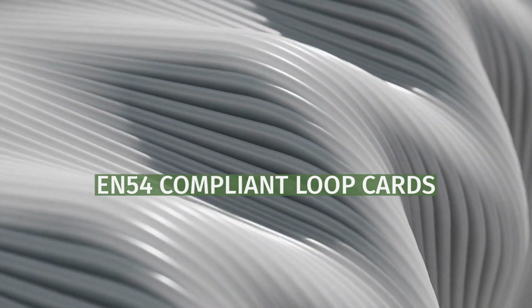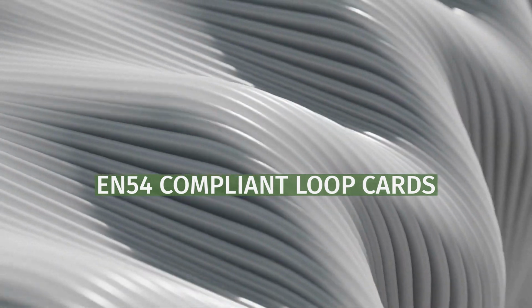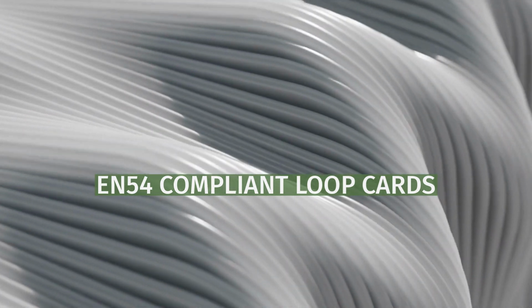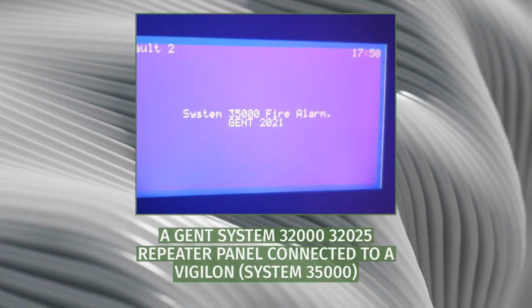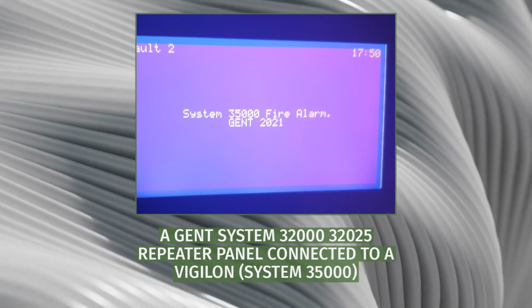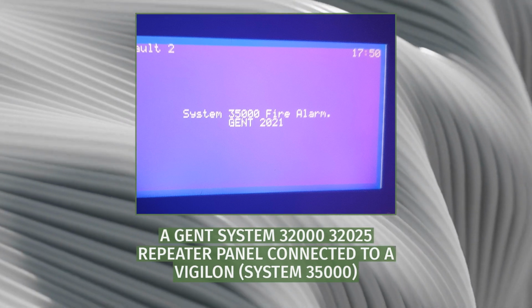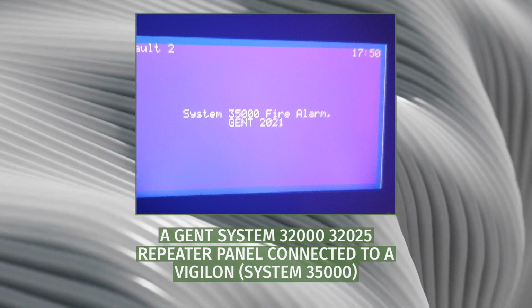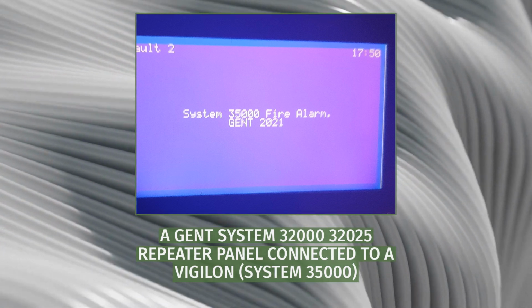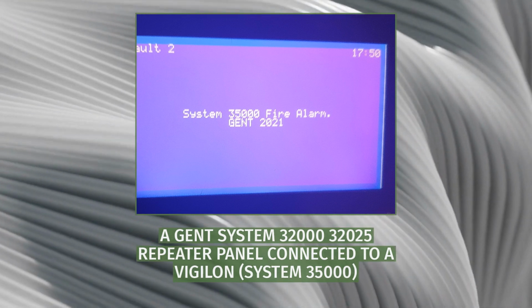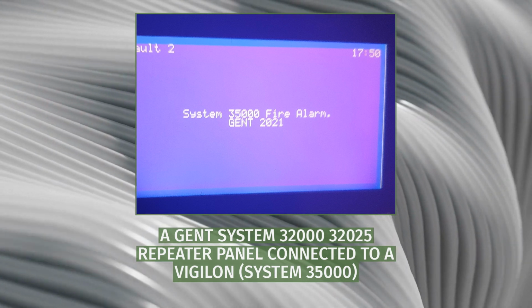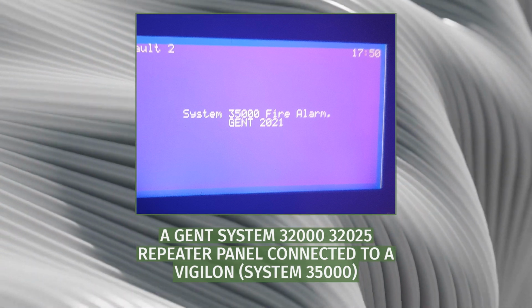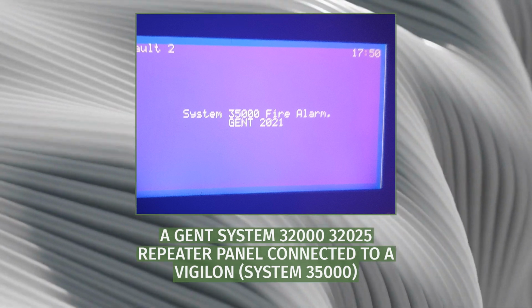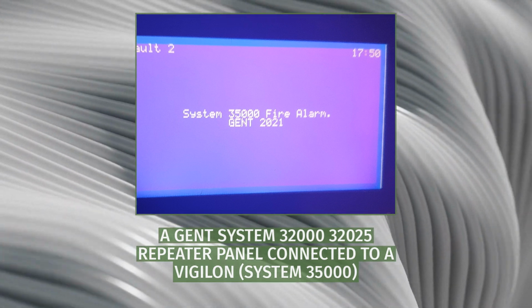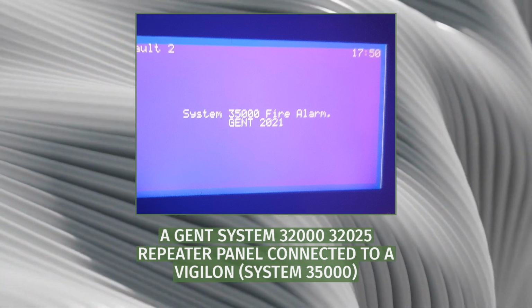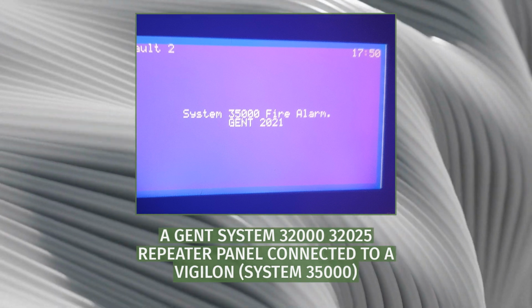In 2014, after the release of the high-power VID S-Cubed and S-Quad devices, Gent released a more powerful loop card that was capable of taking advantage of the full power of these devices. However, despite using the same Gent 2317 protocol, compatibility with some devices, such as earlier S-Quad sounder detectors and 34000 detectors, is limited, and in some cases, such as with some 3400 and 34000 devices, is not available at all. Power output to newer devices is also limited if older S-Quad, S-Cubed, and 34,000 devices are used on the same loop. EN54 compliant loop cards are required for S-Quad self-test detectors.